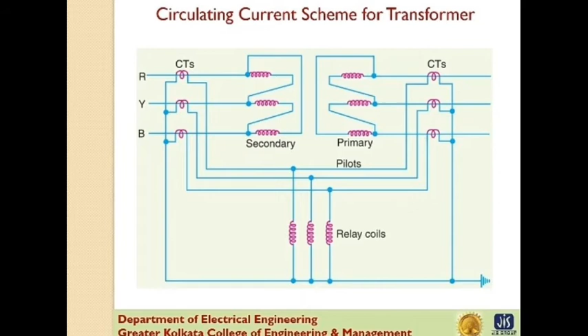The CTs on one side of the power transformer are connected in such a way that the resultant currents fed into the pilot wires are displaced in phase from the individual phase currents in the same direction by an angle equal to the phase shift between the power transformer primary and secondary currents. Now, when the power transformer is connected in star-delta, the current transformers are connected as delta-star. When the power transformer is connected in delta-delta, the current transformers are connected as star-star.